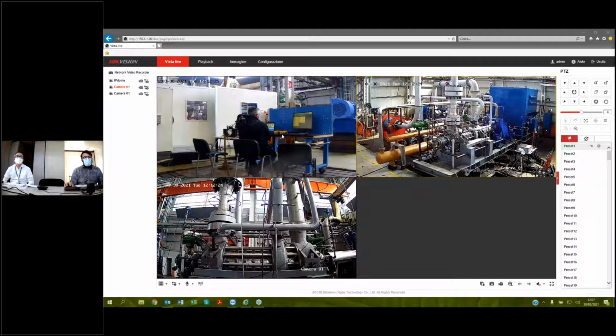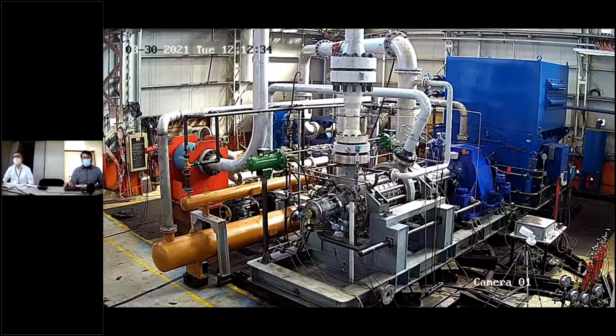A few words regarding the test, and mainly what you are going to see this morning. The group is in the string test configuration. That means that we have the centrifugal pumps, but also all the other equipment in the design configuration. In this case, we have a train composed of the centrifugal pumps that has been discussed by my colleagues, and an electric motor, a huge electric motor of overall power of 6.3 megawatt, and in the middle we have a hydraulic coupling.